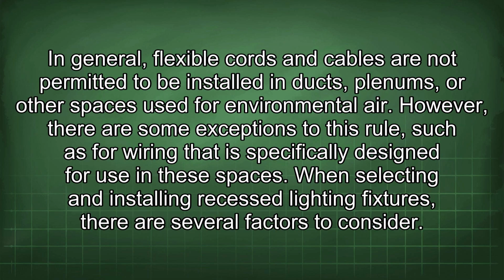In general, flexible cords and cables are not permitted to be installed in ducts, plenums, or other spaces used for environmental air. However, there are some exceptions to this rule, such as for wiring that is specifically designed for use in these spaces. When selecting and installing recessed lighting fixtures, there are several factors to consider.